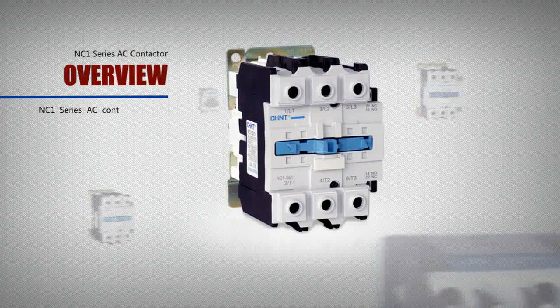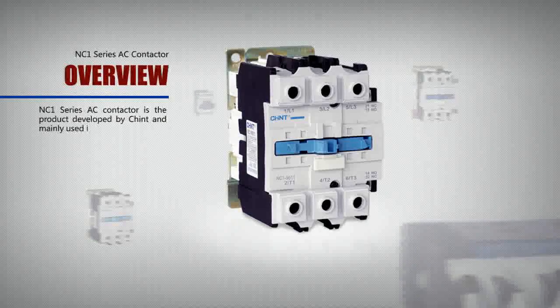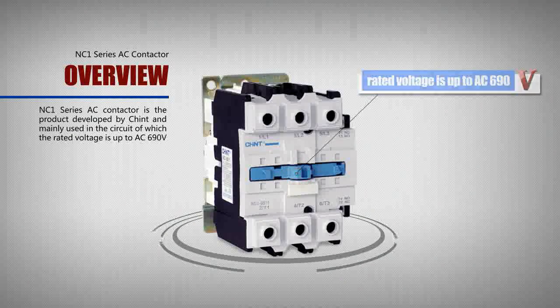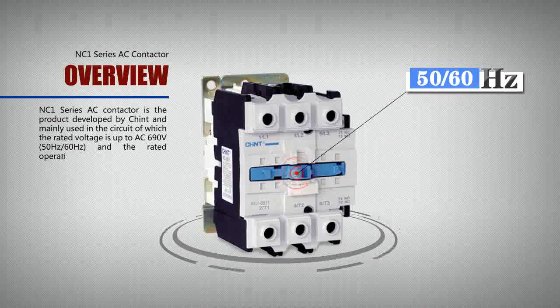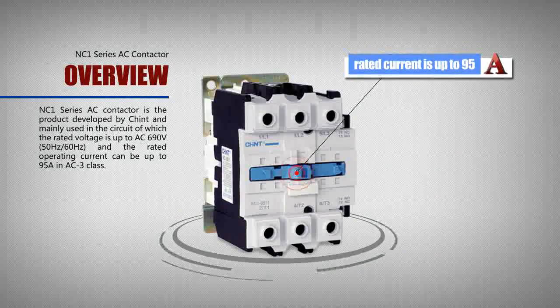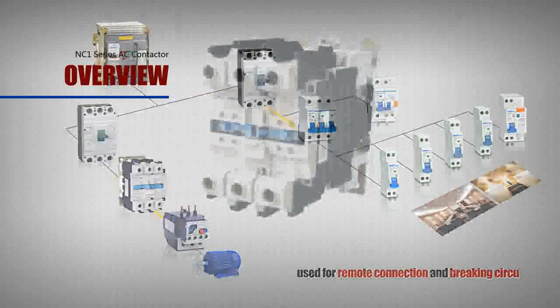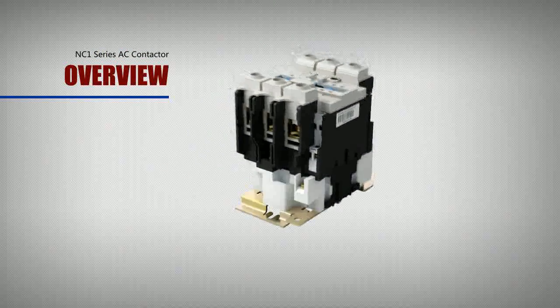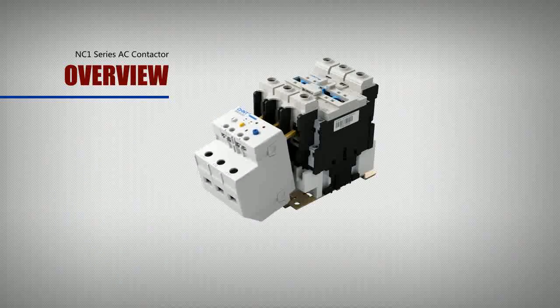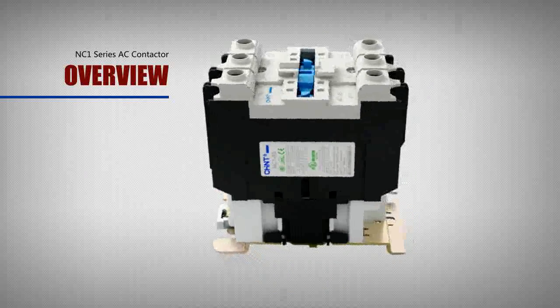The NC1 Series AC Contactor is a product developed by Chint, mainly used in circuits where the rated voltage is up to AC 690V, 50 Hz or 60 Hz, and the rated operating current can be up to 95A in AC3 class. It is used for remote connection and breaking circuits, and can work with a suitable thermal overload relay to form an electromagnetic starter to protect against possible overload. The contactor is suitable for frequently starting and controlling the AC motor.